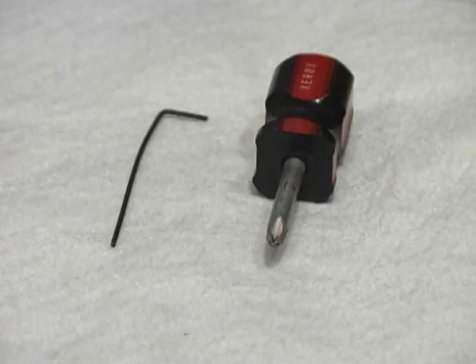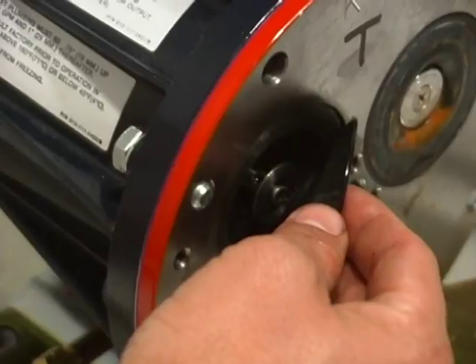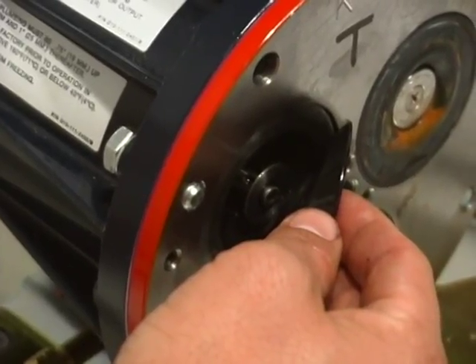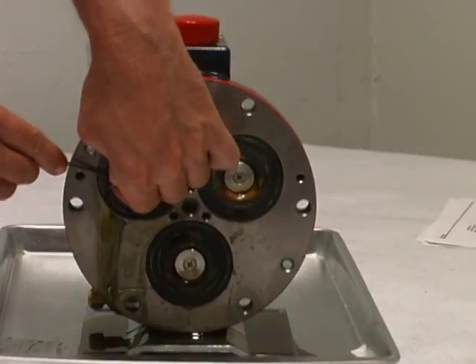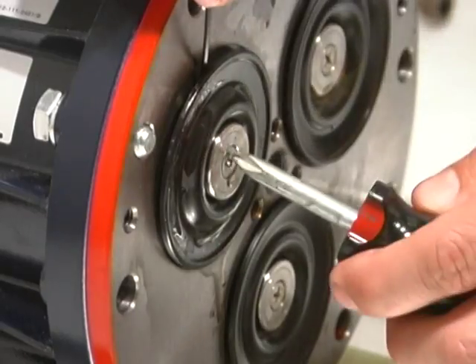If the goal is to remove a diaphragm without damaging it, use a Phillips head screwdriver and a small straight tool such as a small Allen wrench. Gently pull the diaphragm away from the pump and a small hole on the shaft becomes visible. Place the Allen wrench or a small tool into the hole and hold the shaft in place while unscrewing the Phillips screw located in the center of the diaphragm.